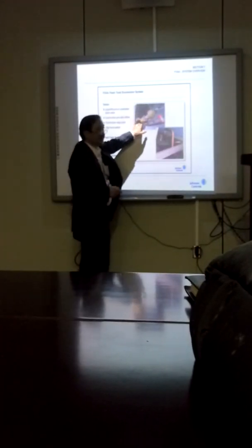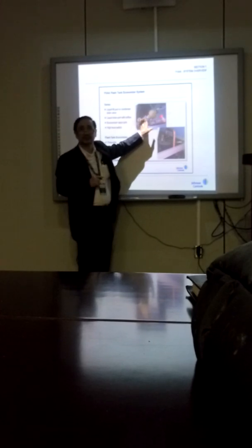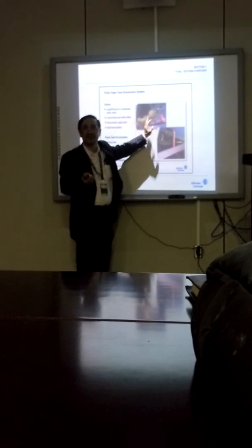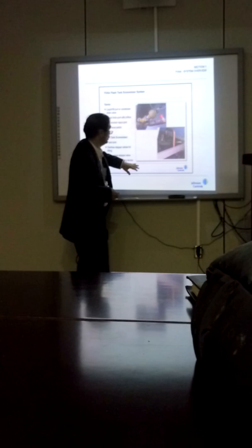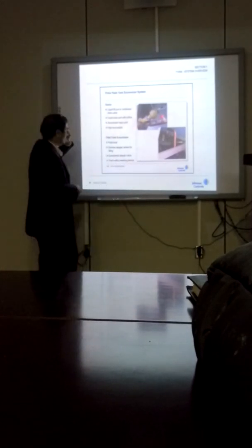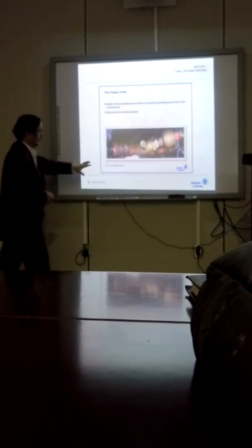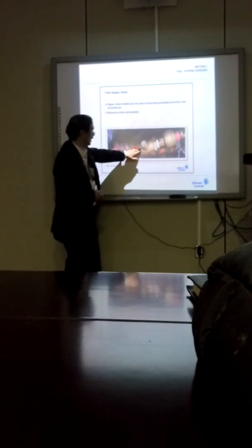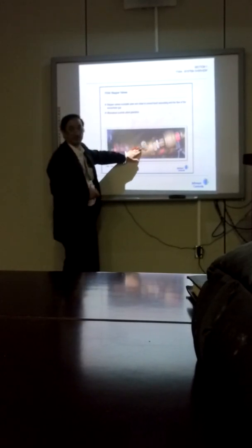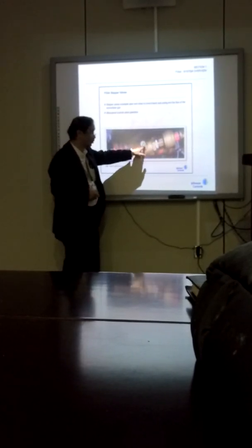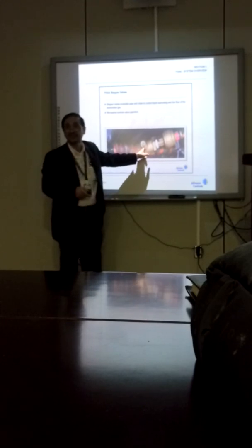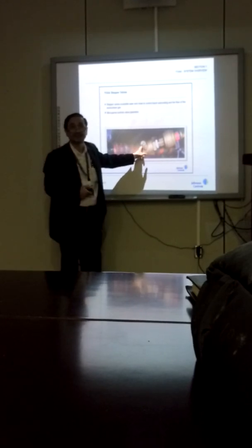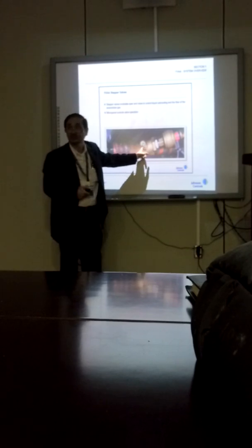This is your stepper motor valve, which we told you is the electronic expansion valve, the feed valve. There are 2 here. One is the economizer, we'll tell you about that. This will look like your electronic expansion valve or feed valve. There's a sight glass here, or moisture indicator also. If it is green, no moisture. If it turns yellow, you have an issue.